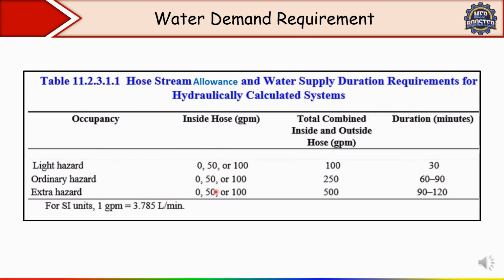So the possible required flow rate for an internal hose station within the building is 0, 50 or 100 GPM, meaning depending on the design need. And an internal hose allowance may or may not apply to a sprinklered building. Okay, then we have a total: use the higher of the sprinkler demand or hose stream. It is the sum of inside and outside sprinklered building hose. Increase the required flow rate by the minimum water based on hazard for firefighting. If you see, in case of light hazard 100 GPM, 250 for ordinary hazard, 500 for extra. I will take one example, 500 GPM.